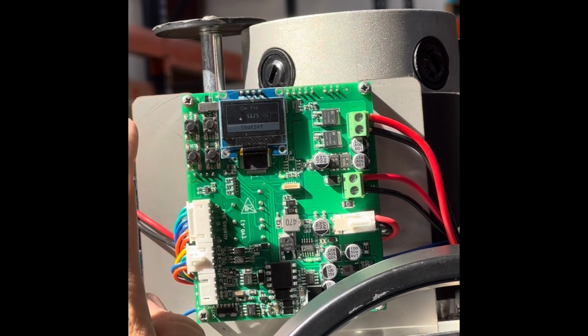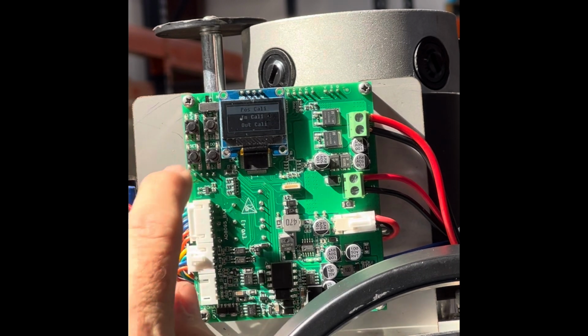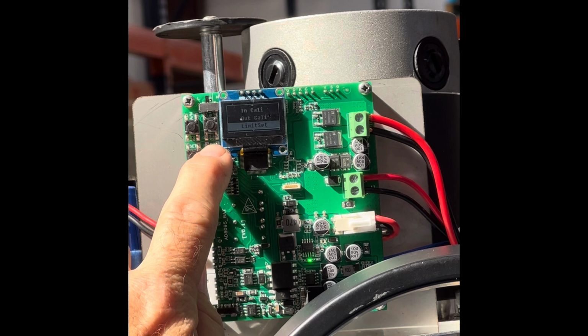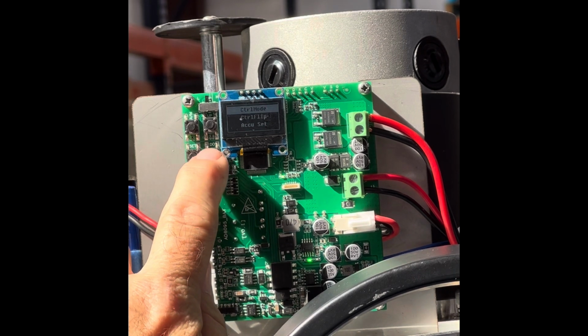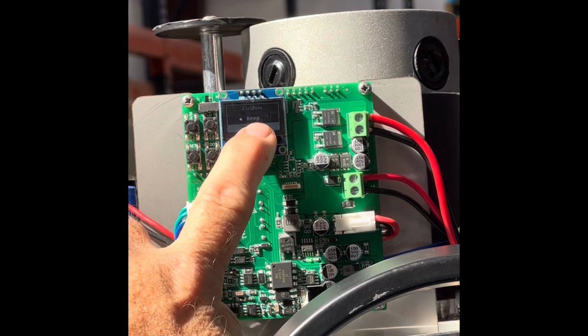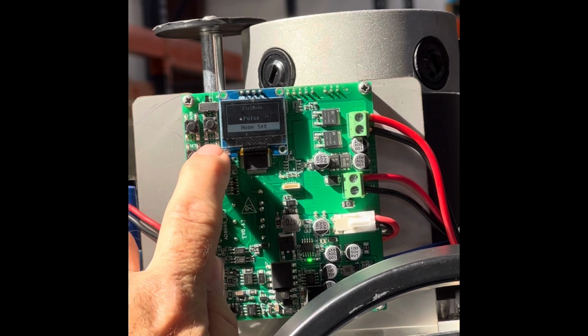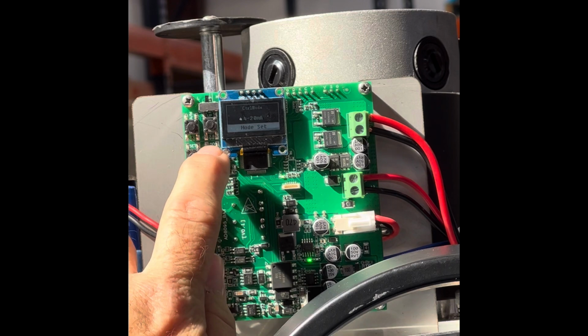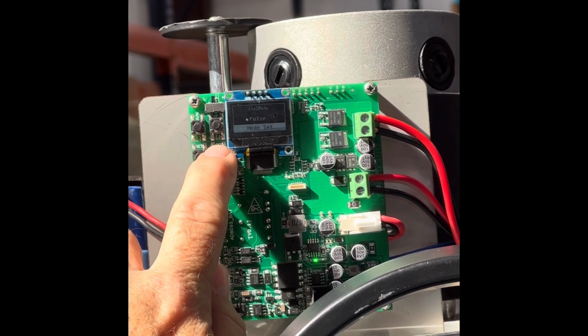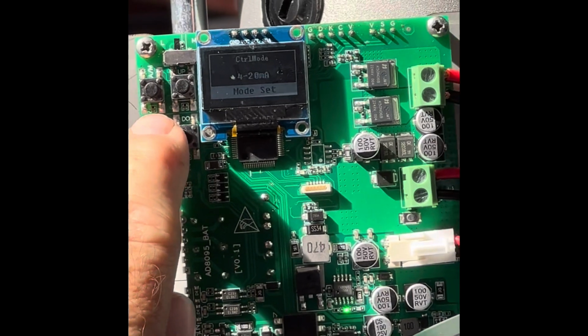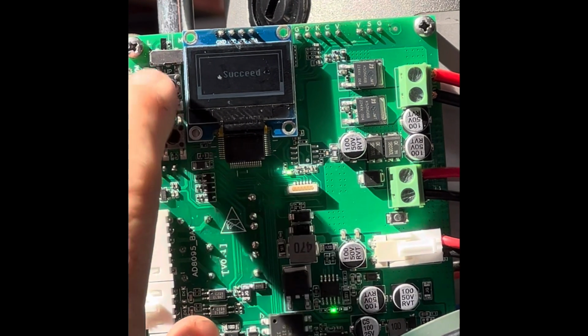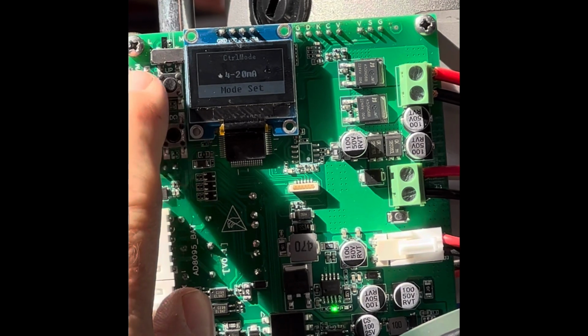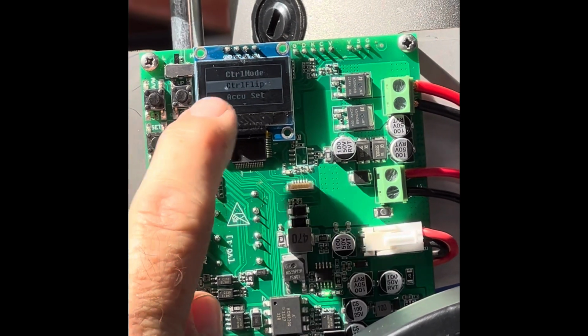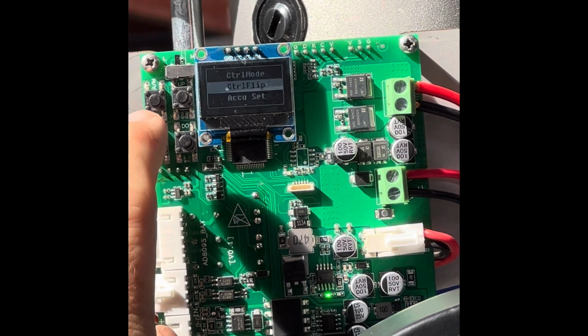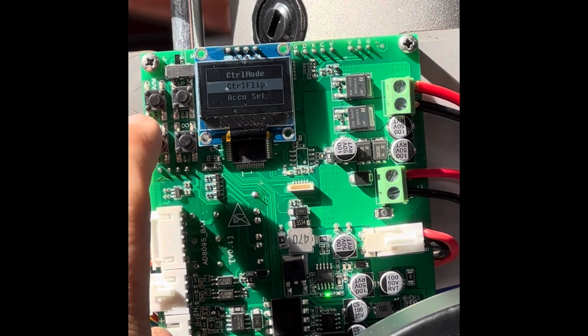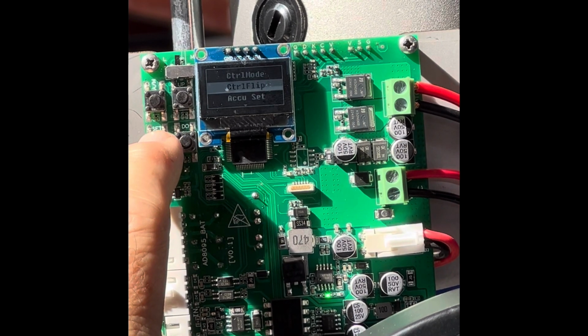Now go back, back, back. Now we're in the main menu. Scroll down to system set, set, control mode. It says keep here. This is where you can change it to pulse or to 4 to 20. So let's change this one to 4 to 20. Okay, now we're going from keep to 4 to 20. Then go back again. It has a control flip, meaning the industry standard is 4 milliamps is closed, 20 milliamps is open. You can flip that. So 20 milliamps would be closed.